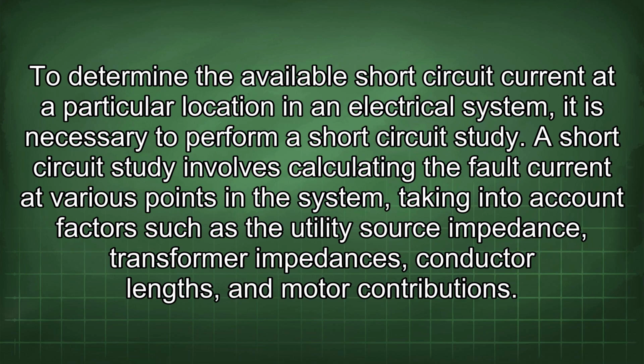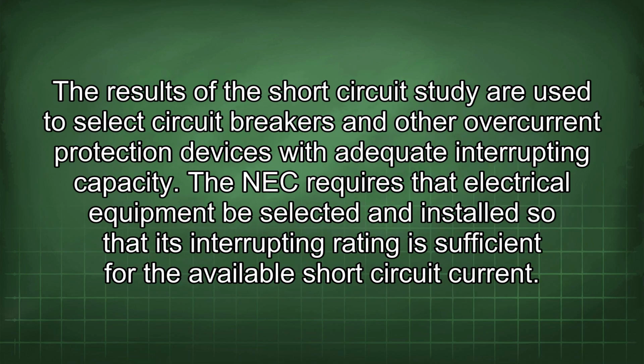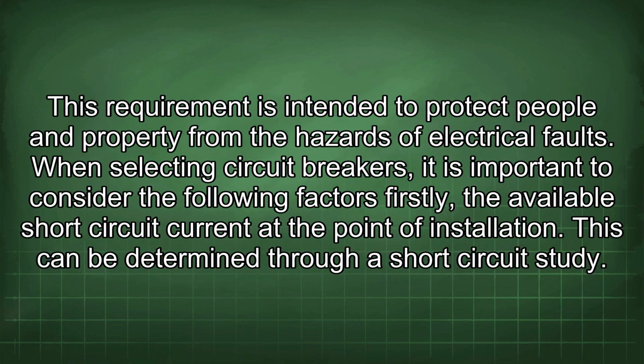To determine the available short-circuit current at a particular location in an electrical system, it is necessary to perform a short-circuit study. A short-circuit study involves calculating the fault current at various points in the system, taking into account factors such as the utility source impedance, transformer impedances, conductor lengths, and motor contributions. The results of the short-circuit study are used to select circuit breakers and other overcurrent protection devices with adequate interrupting capacity. The NEC requires that electrical equipment be selected and installed so that its interrupting rating is sufficient for the available short-circuit current. This requirement is intended to protect people and property from the hazards of electrical faults.